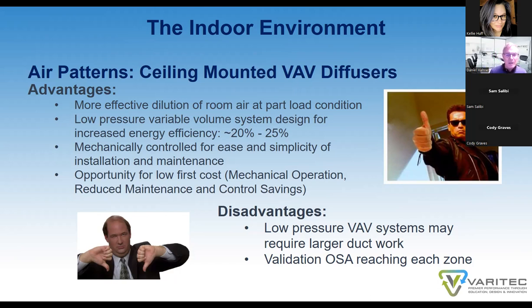digital DDC control technologies. The disadvantages are that low pressure VAV systems will require larger ductwork in a new building. And also, it doesn't offer a solution for validating the amount of outside air reaching each zone.